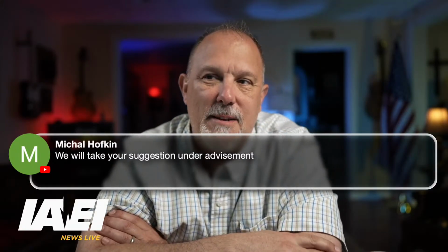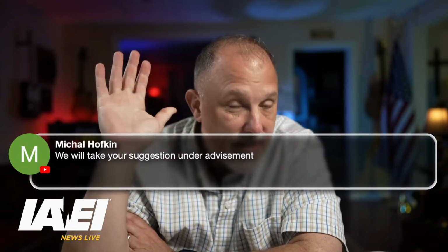What else is on there? You'll know it's going to be marked. You're going to have your identification information, your catalog information, your voltage rating, current rating, short circuit current rating. Now, unfortunately or fortunately, the short circuit current rating is typically going to be a recipe on the door of a panel board. And Michael Hofkin, we will take your suggestion under advisement. Is this like a public input, Michael? Should I make a formal public input? I'm just saying. I'll look forward to that change.